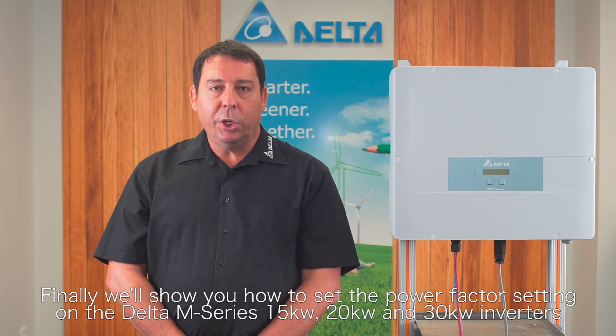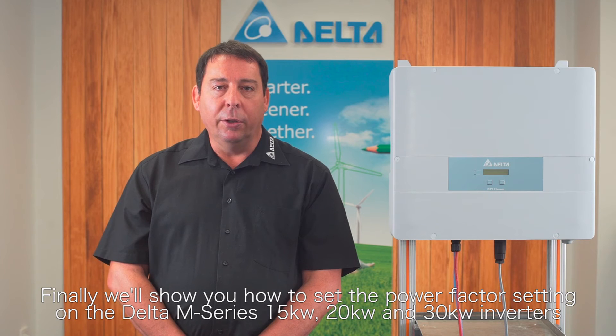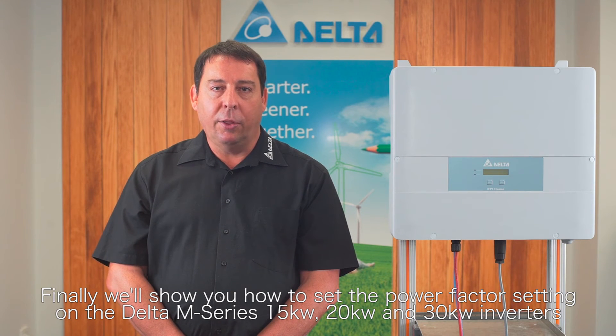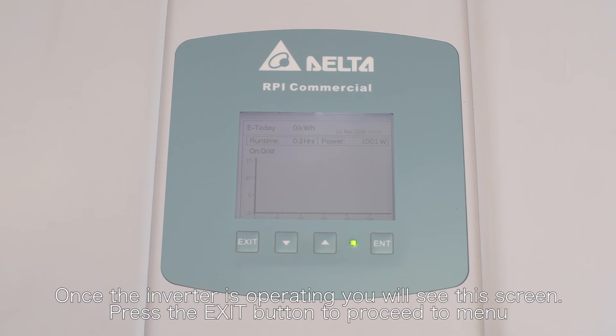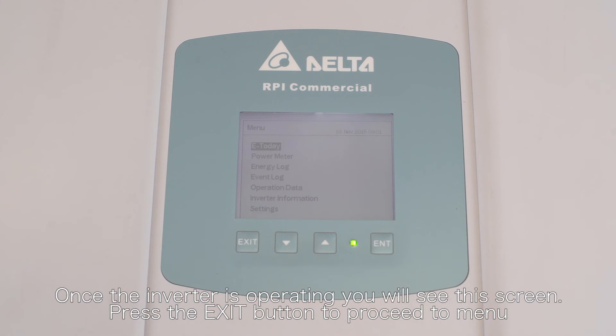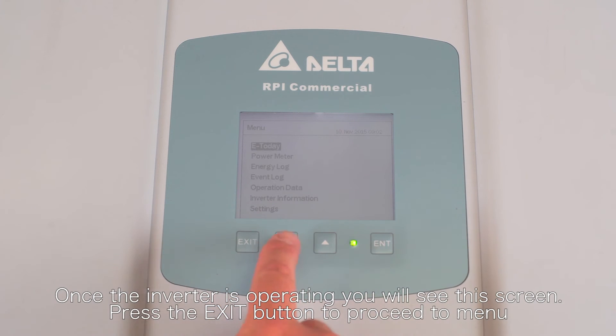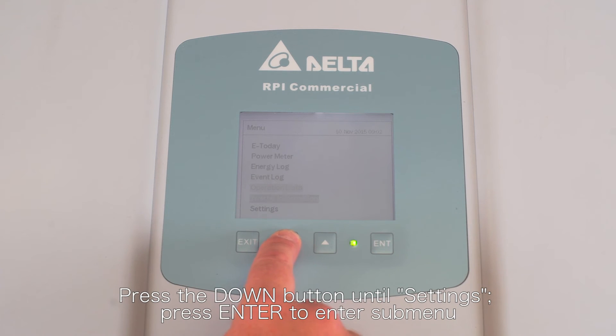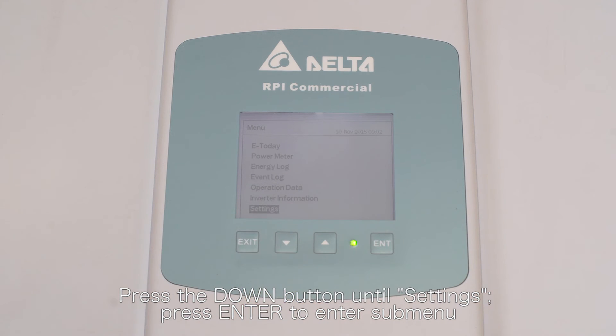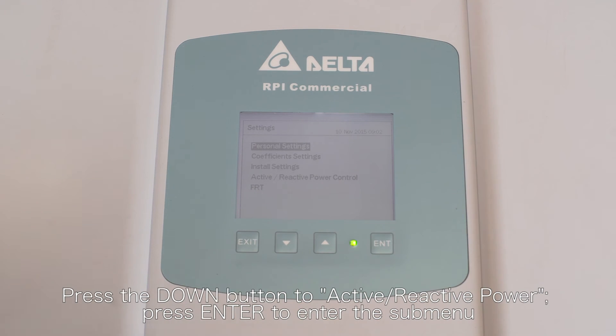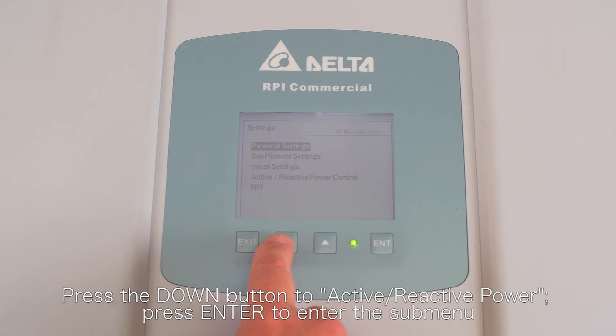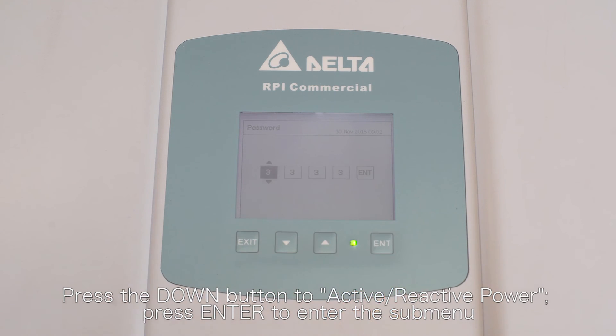Finally, we'll show you how to set the power factor setting on the Delta M series 15, 20, and 30 kilowatt inverters. Once the inverter is operating you will see this screen. Press the exit button to proceed to the menu. Press the down button until settings is shown, then press enter to enter the submenu. Press the down button to active reactive power and press enter to enter the submenu.